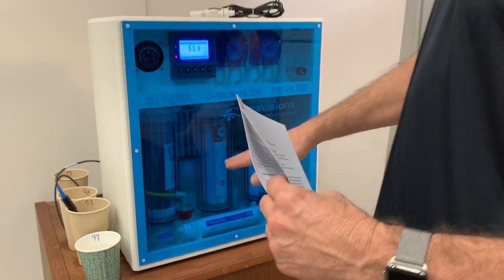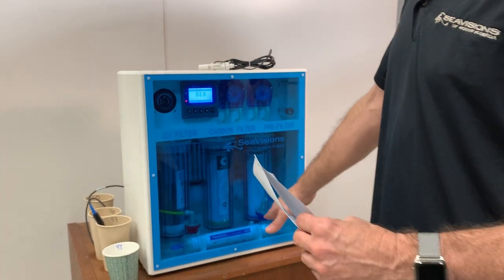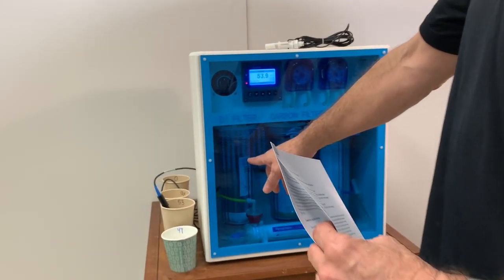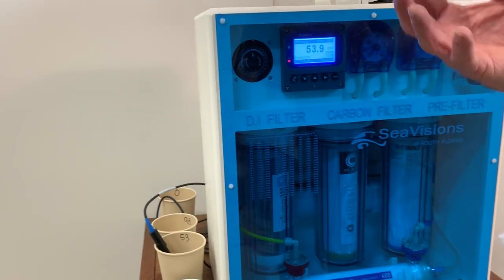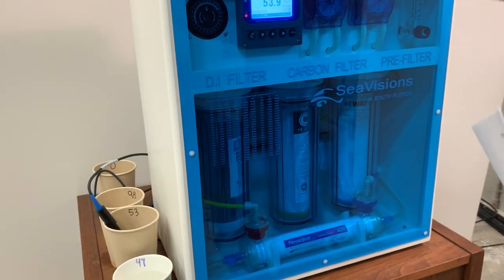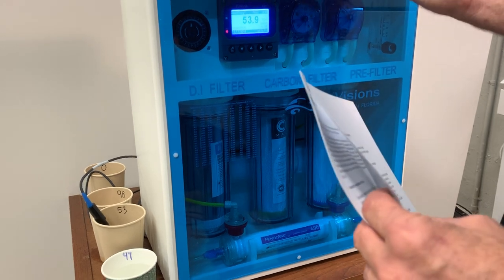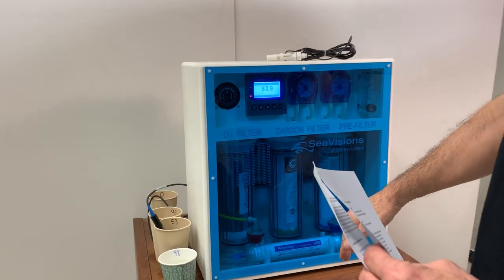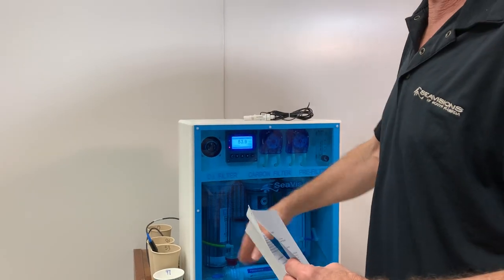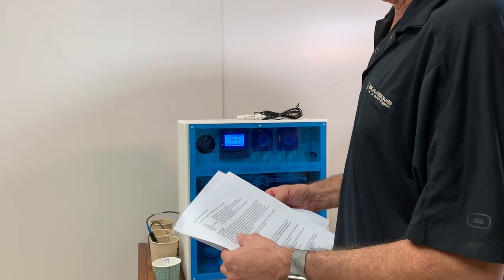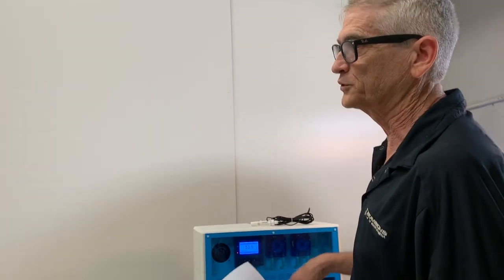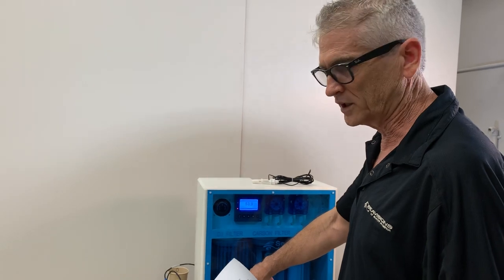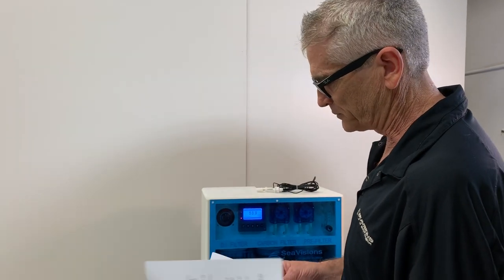Again, another way that you can change these is by looking at your DI filter. If your DI filter gets consumed, if you have high TDS in your water and some of that high TDS is getting through your RO filter, your DI filter is going to consume faster. You might want to consider a pre-filter before this machine to save on expense of the DI filters.